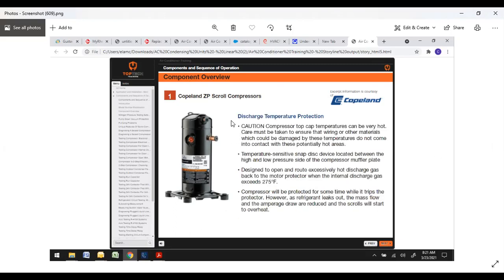It does have built-in discharge temperature protection. Now this is important to know here. Invariably, you'll come across overheated compressors. The temperature-sensitive snap disc is located between the high and low pressure side of the compressor muffler plate. So kind of know where that is, so you can direct your water to cool down the compressor.